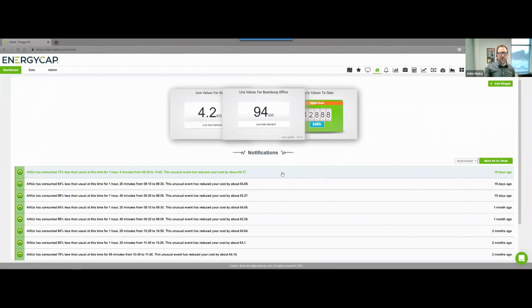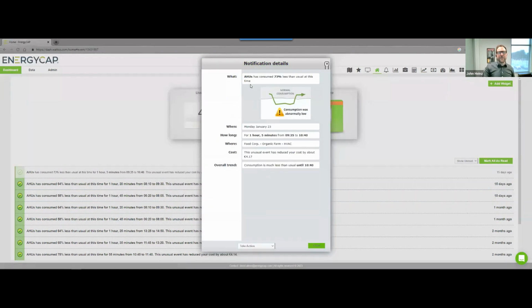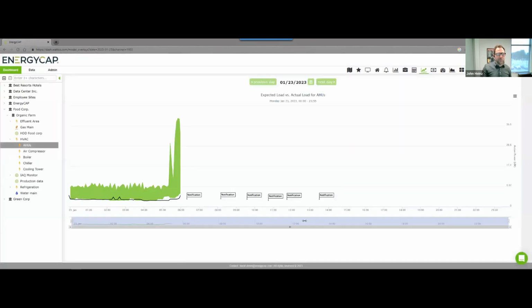Here's how this looks in practice. If I go back to my home screen, we have all these notifications—a few days ago I was alerted that there's a problem with one of my points. If I click on this, it's telling me an air handler unit consumed 73% less than usual. So it went well below the Sentinel, and it provides some other details. This is the type of view you could get in a text message or on the notification screen, and if I want to see where this displayed on the Sentinel view, I can click on that and see what's going on.